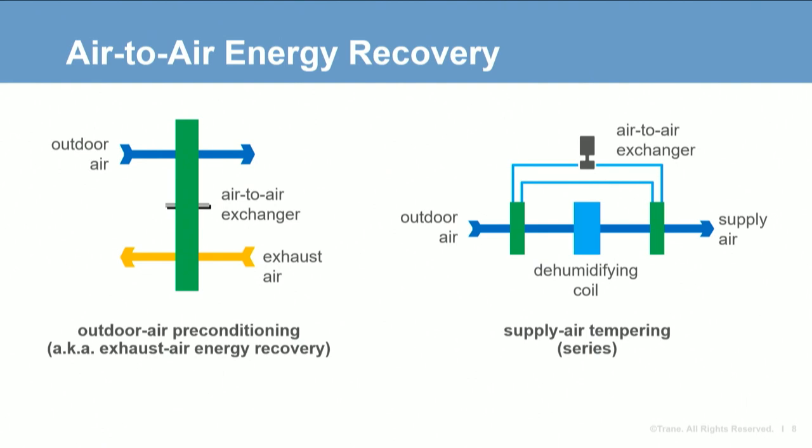Another configuration recovers heat from either a separate airstream or a different location in the same airstream, and uses it to reheat air that has been dehumidified. In the series configuration shown here, the air-to-air exchanger removes sensible heat from the entering outdoor air upstream of the dehumidifying coil, then transfers that heat to reheat the air downstream of the coil. We often refer to this as supply air tempering.